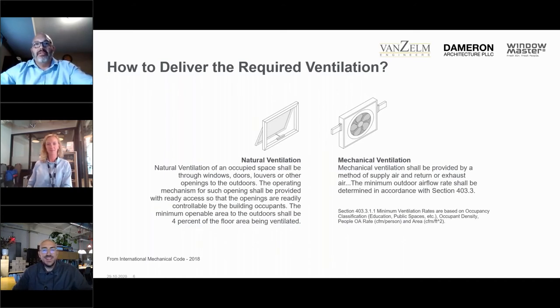the ventilation being natural or mechanical, it can be brought in, obviously, through the use of operable doors, windows, or louvers. And there are strict requirements in the mechanical code that tell you how much opening area is there to meet the requirements of the space. So in a natural ventilation mode, you have to have 4% of the floor area that area is being served. It's typically what the current findings are from the IMC to make sure that you're adequately ventilating the space naturally. In a mechanical ventilation mode, it looks at both the number of occupants and the type of space it is, as well as the area. So it's both a function of the number of people, the use, and the square footage. So for instance, in an office, you're required to deliver 5 CFM per person in there, plus 0.06 CFM per square foot of area. So it looks at both the number and how big the room is to make sure that the amount of ventilation being brought in is adequate for the space being served.